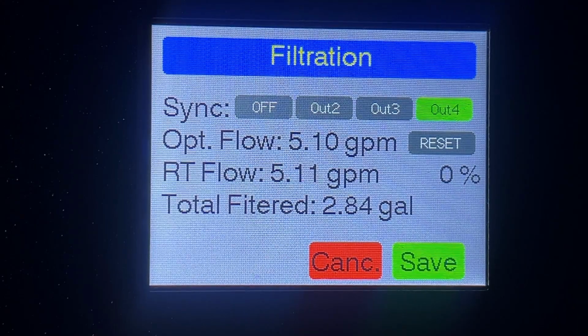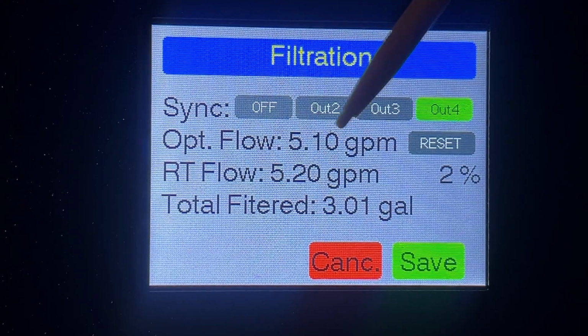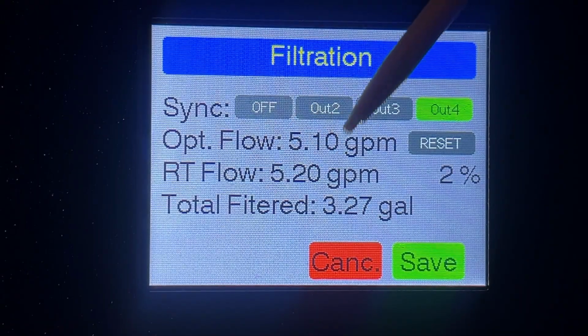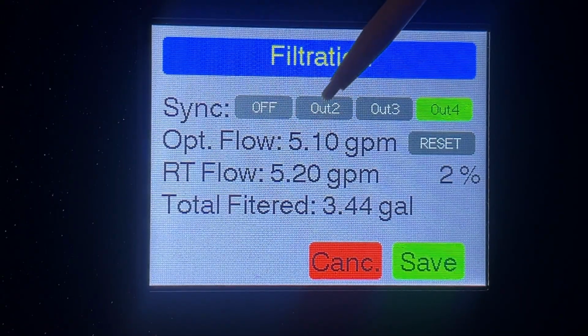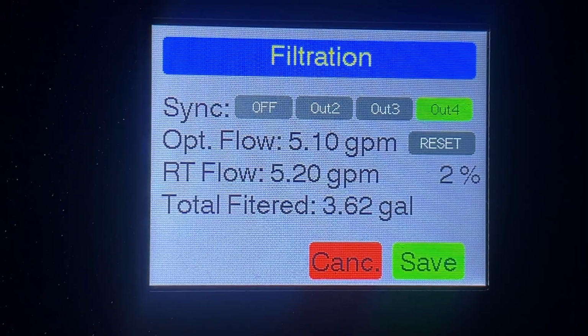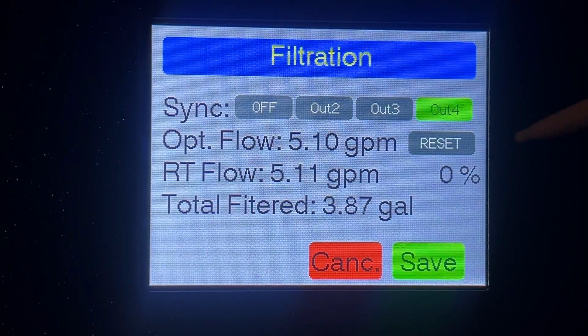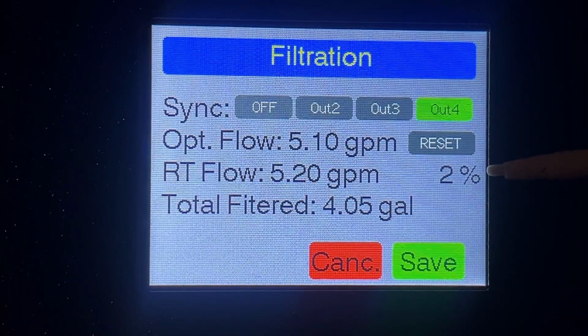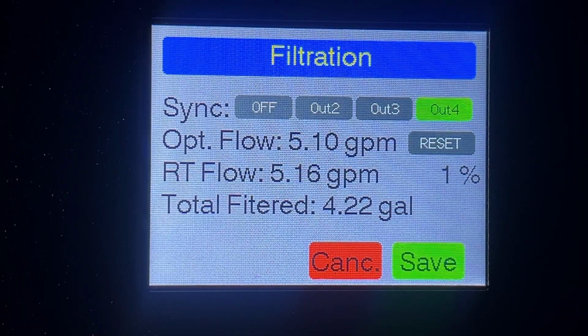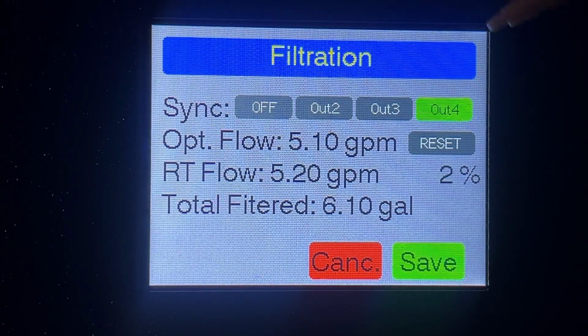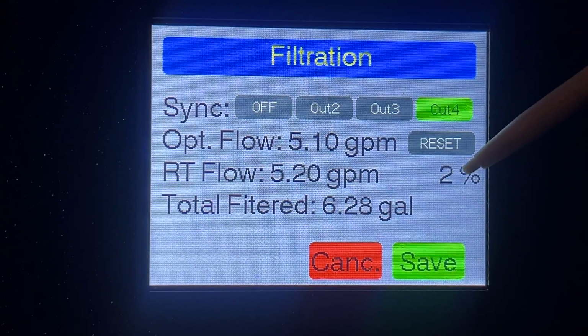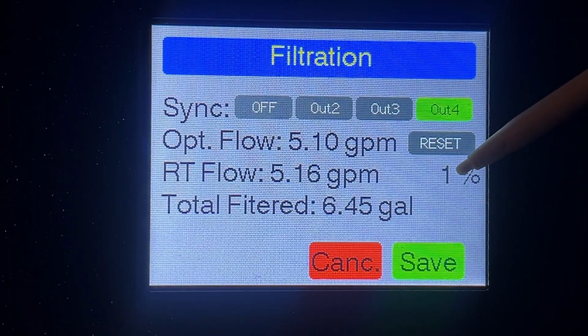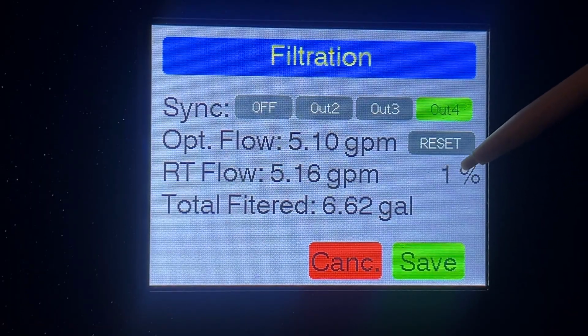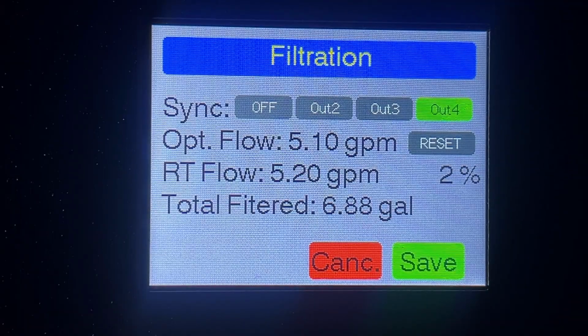Okay, what it's telling us right now is our real time flow is 520. Our optimal flow is around 5.1 because it's the average over the 30 seconds. So right now we are at 0, or 2% above our optimal flow. When we see this number decrease, like minus 20%, minus 30%, it means the filter is clogged and it needs to be replaced.